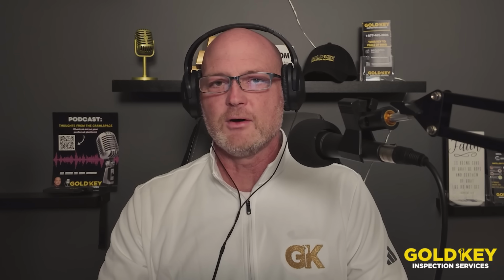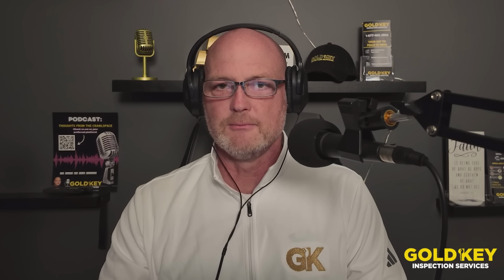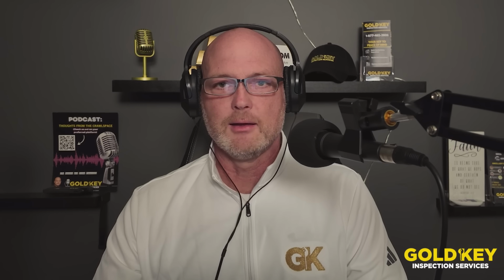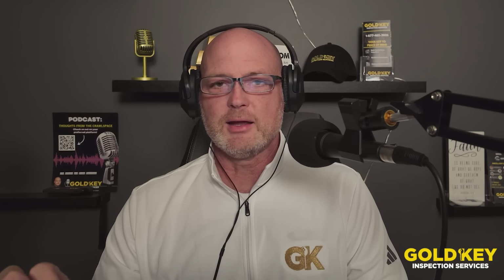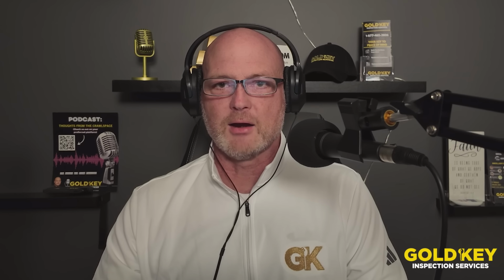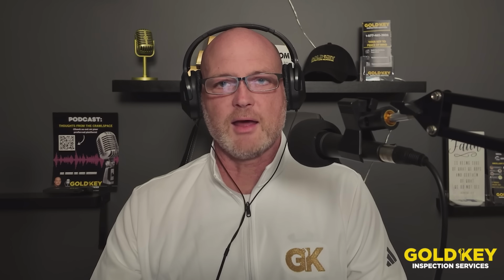So here's one thing that we do not do: we cannot run the air conditioner in cold weather. There are some folks that say you can do that, and they choose to do so. And there is a little value in knowing, hey, does this unit at least come on? It's 45 degrees outside. It may come on, but generally there are oils in the compressor that are kind of congealed. And when it's cold, they just don't want to move very well. And so you risk damaging the unit if you turn it on when you have that kind of situation. And we don't want to risk that. And there's not a lot you could tell anyhow.